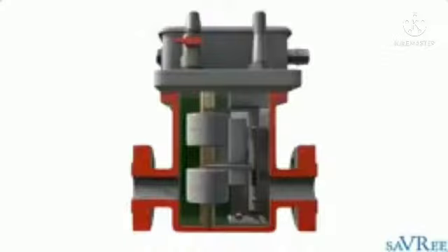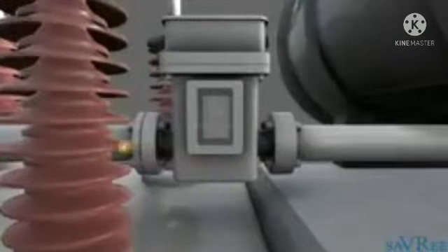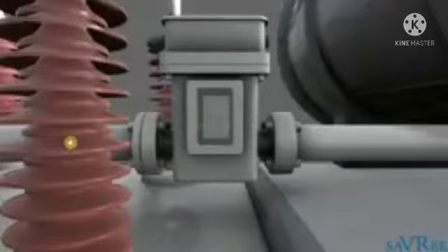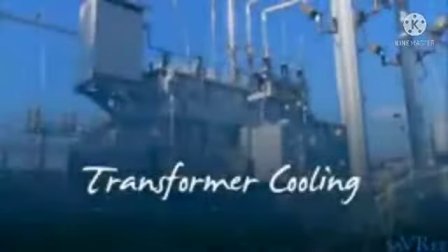The Buchholz relay itself has a third and final feature, and that is to shut down the transformer in the event the insulating liquid level becomes low. We can see that it's installed between the conservator tank and the main tank. If the level was to come down to here, we would trip the transformer, and that protects the transformer and ensures that we do not get a catastrophic failure.